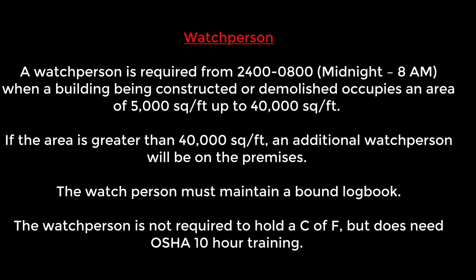A watch person is required from midnight to 8 a.m. when a building being constructed or demolished occupies an area of 5,000 square feet up to 40,000 square feet. If the area is greater than 40,000 square feet, an additional watch person will be required on the premises. The watch person is not required to hold a certificate of fitness, but is required to have the required OSHA training.